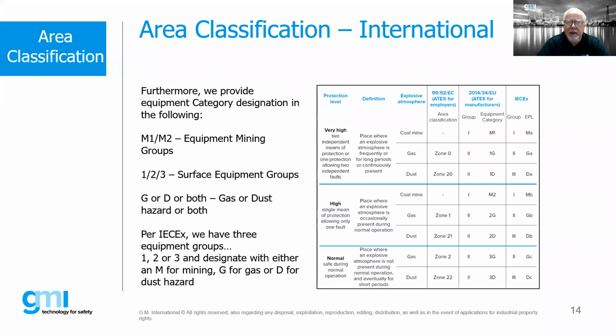We can also find G or D. Those stand for either gas or dust hazards, and so forth. So the important thing to remember from this point is, again, understand that equipment that has very high independent means of protection is suitable for zone 0, which is an area in which it's continuously present. A high level, which would be a single fault and still provide safety, would be suitable for environments in which gases are occasionally present during normal operation. We would consider that to be a zone 1 area.